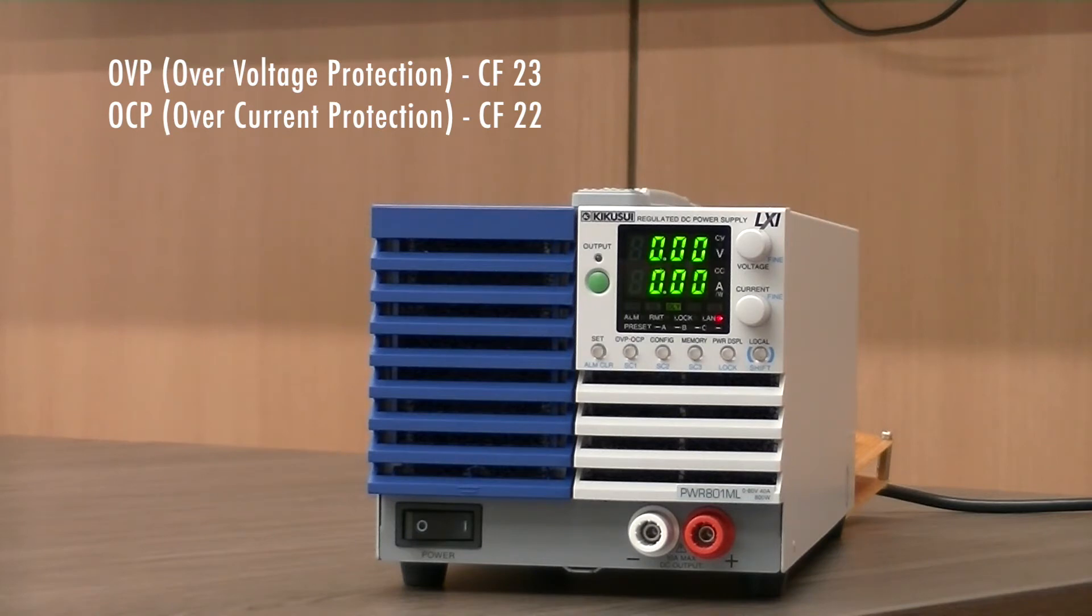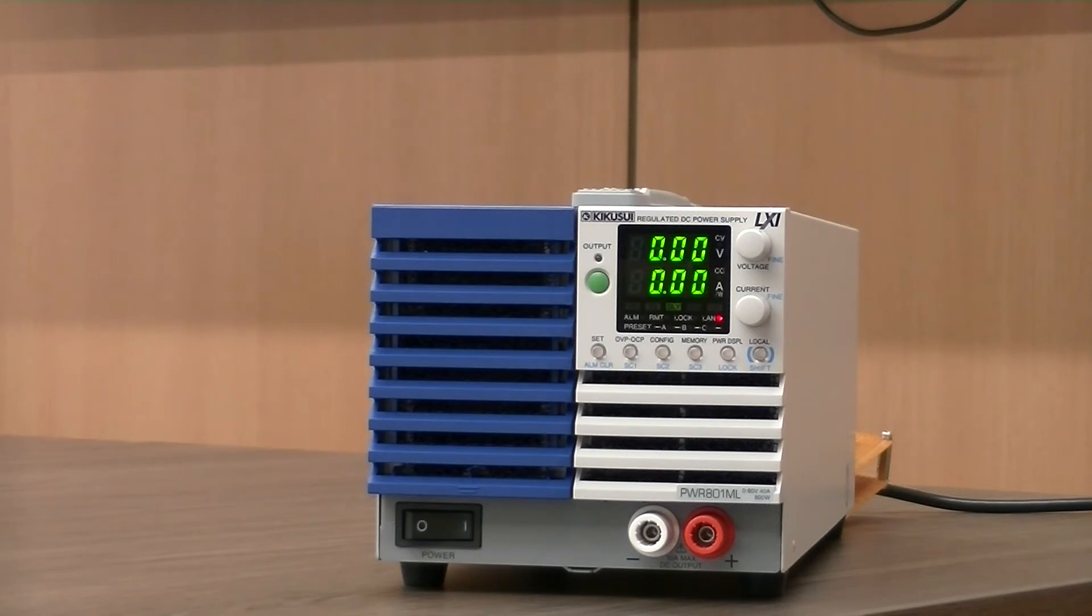Anytime the output terminal voltage or current exceeds your desired trip point, the OVP or OCP protection function is activated and output is prevented. Another standard protection that is included on the PWR801ML is OHP or overheat protection.